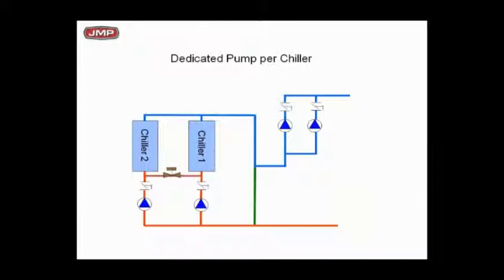And we kind of play with this a little bit to see if you want to stand by. We could just add a butterfly between the two chillers there and show them. Now you've got either pump to either chiller. You've got a great little primary-secondary setup, put a dedicated pump per chiller.